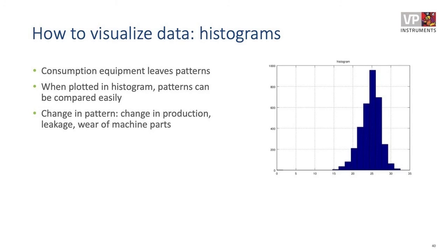That's about an example in the automotive industry, and that made me think of a visit I had earlier this year in a plant in the USA where they used argon. It's not about compressed air in this case; it's about argon welding gas, and they were spending around $165,000 on argon each year, coming from a liquefied argon storage tank. And they purchased one flow meter from us, so roughly $1,500, to measure it. And guess what? They found out that 50% of the argon was being wasted. So that was around $80,000 a year of waste identified.